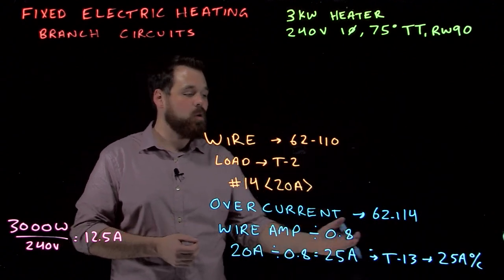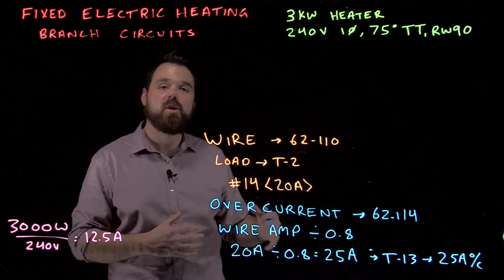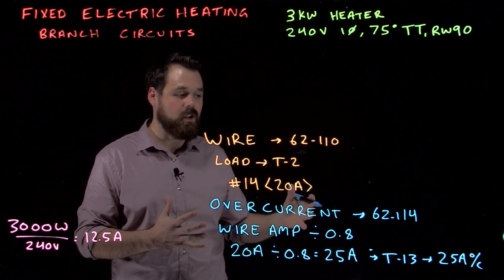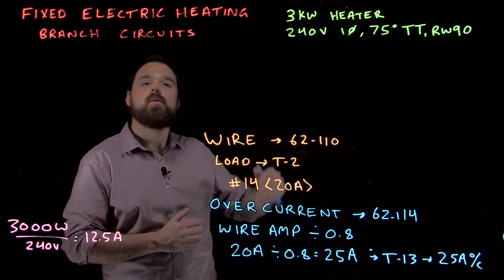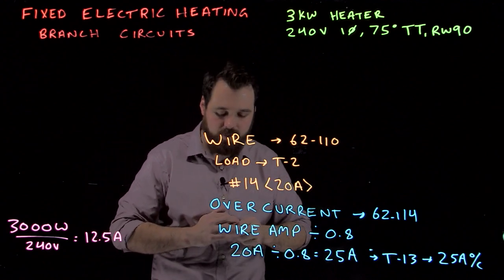If a 25 amp overcurrent did not exist, subrule 8 tells us we are allowed to go to the next higher level. So if there was no 25 amp breaker, we would go up one level and we would get to a 30. But there is a 25, so we are going to take a 25.